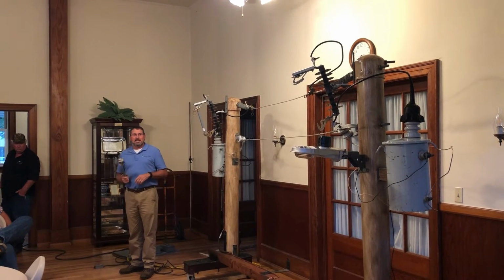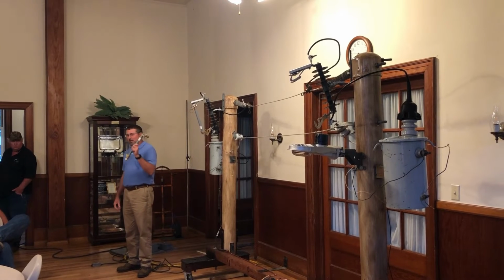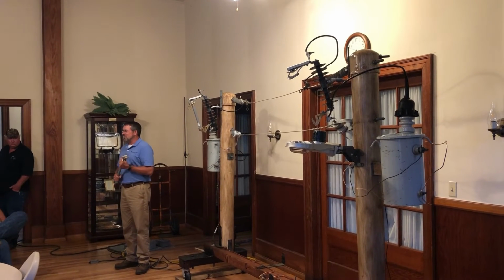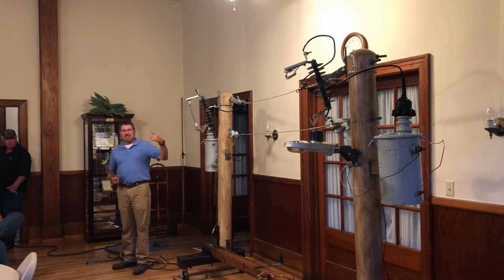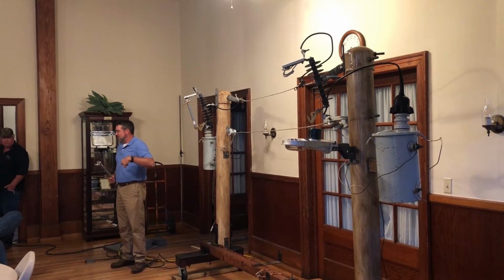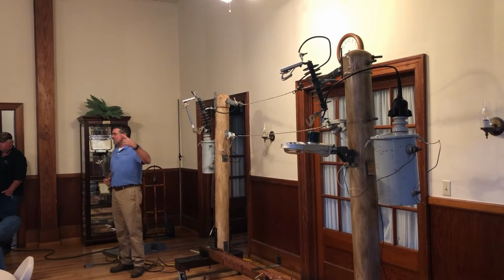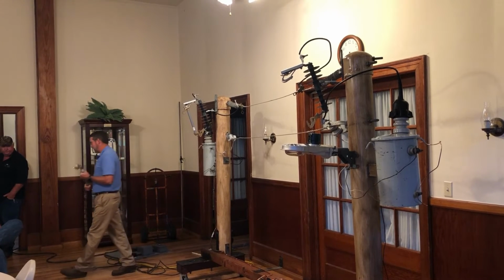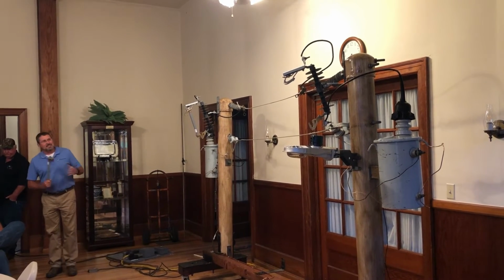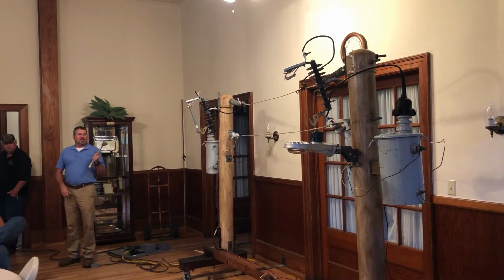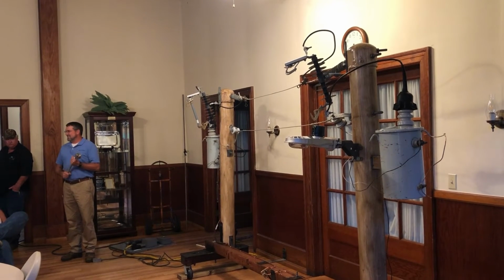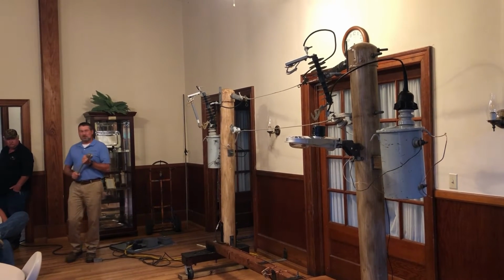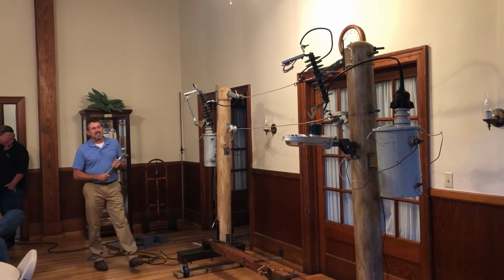On a delta bank transformer, you can have one of these hanging open, but it's still energized because it's being fed through the other two transformers, since it will backfeed through. Again, like John was saying earlier, you can't see it, you can't smell it, you don't know if it's hot or if it's not.